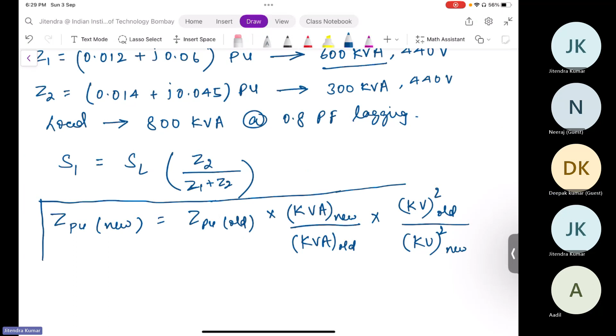Sir, why are we doing this? We are converting impedance to the same base level so that we do not mess up while computing load sharing of each transformer. We have to bring them to the same base level, because if you plug in the value of Z1 with a base value of 600 kVA and 440 volts, and plug in the value of Z2 with 300 kVA and 440 volts, you will get a bizarre result. We don't want that to happen.